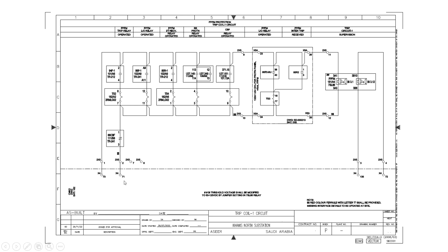In order to save the trip coil in the circuit breaker failure condition, there is a scheme called Save Trip Coil. When a self-reset relay operates there is no problem — it resets when the fault finishes. But when 86F1 or any other lockout relay operates, it will be operated continuously and the circuit breaker fails to operate.